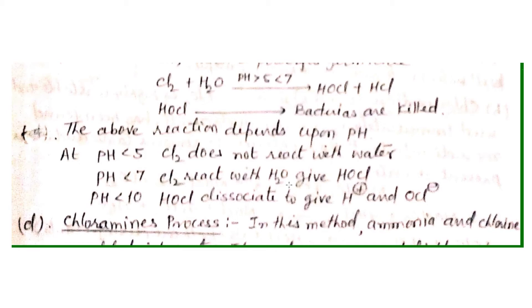Regarding pH ranges: if the pH of water is less than five, chlorine does not react with water. If the pH is between five and seven, chlorine reacts with water to give hypochlorous acid. If the pH is between seven and ten, HOCl dissociates to give H⁺ and OCl⁻ ions. So the perfect pH range for producing nascent oxygen and effective disinfection is five to seven.